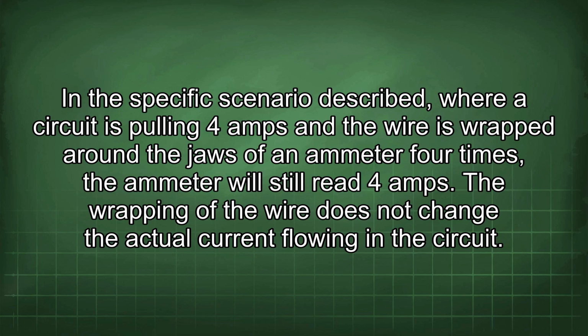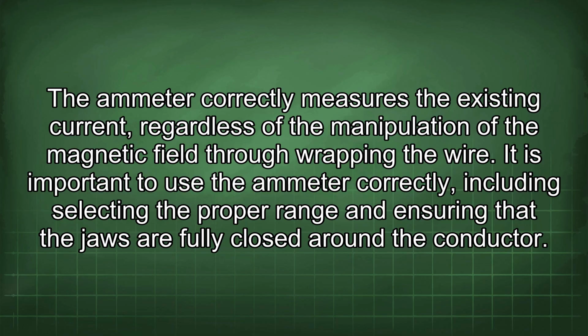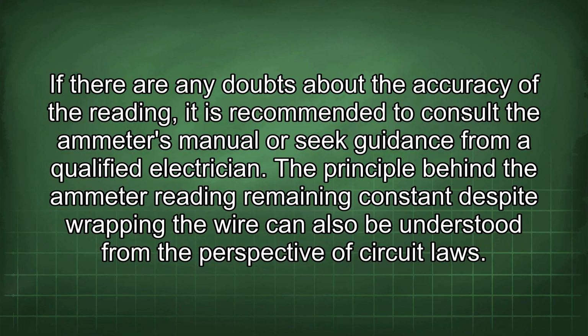The wrapping of the wire does not change the actual current flowing in the circuit. The ammeter correctly measures the existing current, regardless of the manipulation of the magnetic field through wrapping the wire. It is important to use the ammeter correctly, including selecting the proper range and ensuring that the jaws are fully closed around the conductor. If there are any doubts about the accuracy of the reading, it is recommended to consult the ammeter's manual or seek guidance from a qualified electrician.